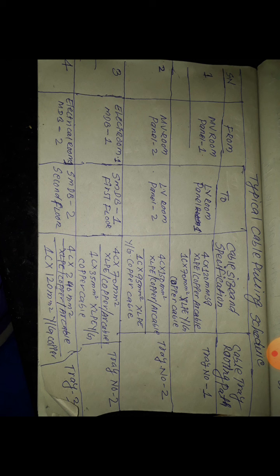So this is cable tray or cable ladder number 1. The last entry shows 4 core 120 square, and another line shows 1 core into 70 square XLPE YG copper cable. This means, as I already told you, the power cable half value needs an earthing cable, the yellow-green cable, because earthing is most important for safety.